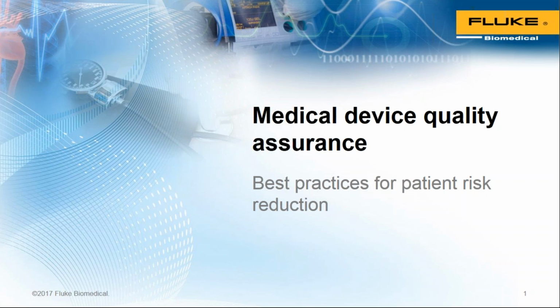But the real critical devices, the patient monitors, the defibrillators, and so forth, we will need to establish a frequency of inspection. That'll come from the manufacturer. And we can also do our own independent risk-based assessment. We should come up with the same frequency of inspection as the manufacturer is recommending. That work has to be done.